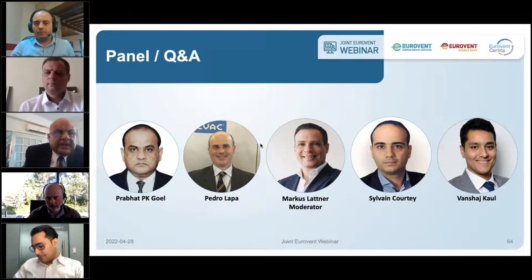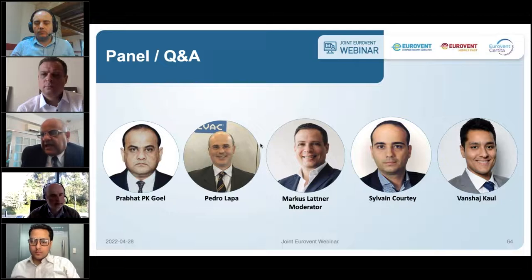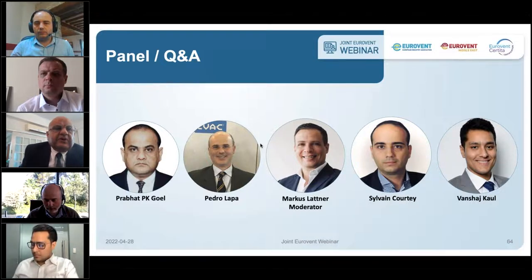If you look at ASHRAE 90.1, then ASHRAE 90.1 classifies the whole Middle East and India and other places as region zero or region one. And it says economizers are not mandatory. And that's why you didn't see much of economizer operations in the Middle East or in India.